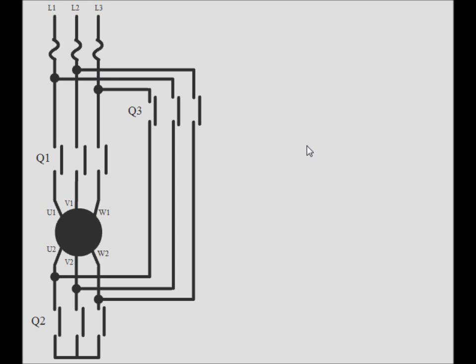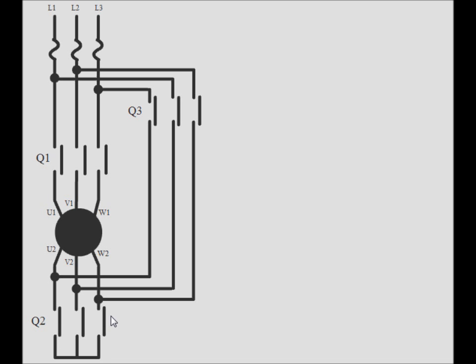So this is the power circuit for a star delta starter. These are basically fuse or overload and then Q1 contactor here and there is a second contactor Q2 to make the motor run in star mode. Initially Q1 and Q2 will operate and motor will run in star mode. After some time Q2 will open and Q3 will close and motor will run in delta mode.